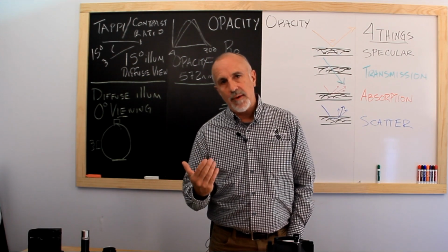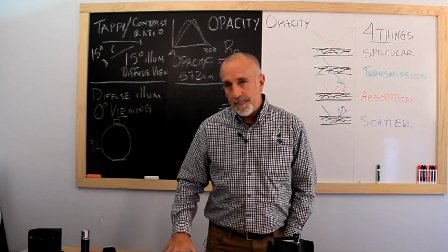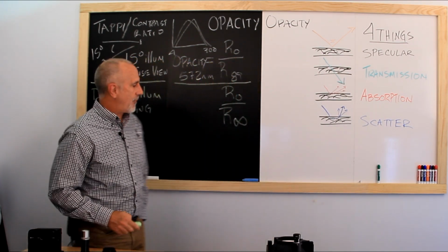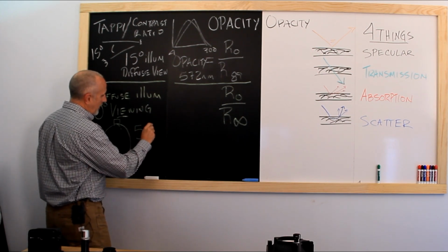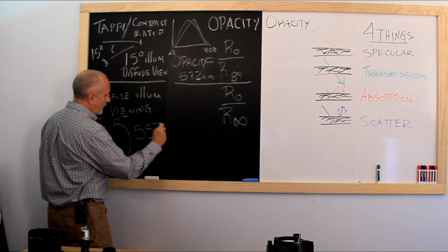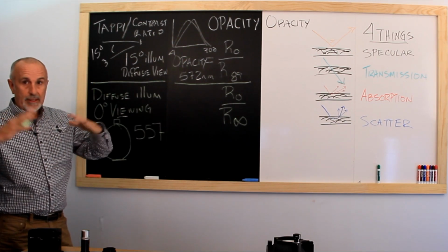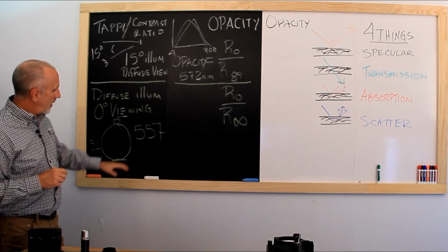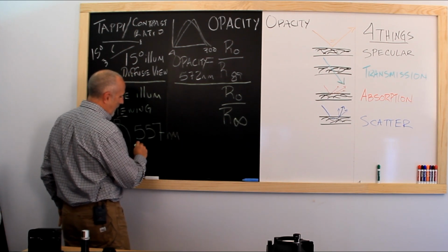And the Y function represents the center portion of that, which is the green region of the spectrum, with the dominant wavelength being 557 nanometers. So, measuring light, it's a broadband filter, much like the TAPPI method is here. It's looking at a fairly large region, but with most energy in the center portion of the spectrum, and that measures at 557 nanometers.